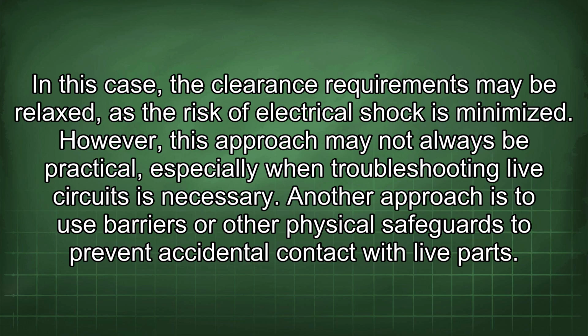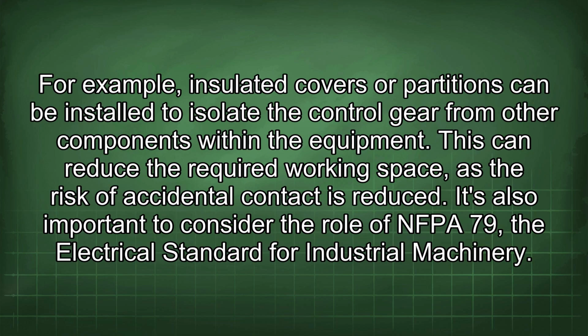Another approach is to use barriers or other physical safeguards to prevent accidental contact with live parts. For example, insulated covers or partitions can be installed to isolate the control gear from other components within the equipment. This can reduce the required working space, as the risk of accidental contact is reduced.